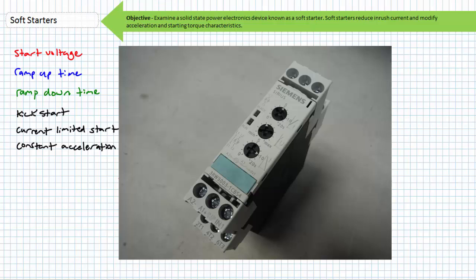While we're taking a look at this particular soft starter, note the 2 indicator LEDs, ready and run. Since soft starters are solid-state devices, it's impossible to tell if they're enabled, unlike an electromechanical contactor or relay that physically moves when the coil is energized and is accompanied by a characteristic sound. It is for this reason soft starters often use indicator LEDs.